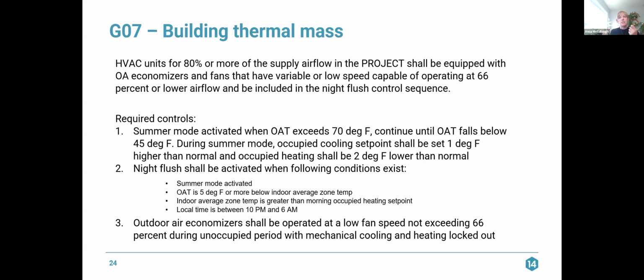So we're going to have summer mode and winter mode. Summer mode is activated when outdoor air temperatures exceed 70 degrees and continues until outdoor air temperatures fall below 45 degrees. During summer mode, the occupied cooling set point shall be set 1 degree higher than normal, and the occupied heating set point shall be 2 degrees lower than normal.